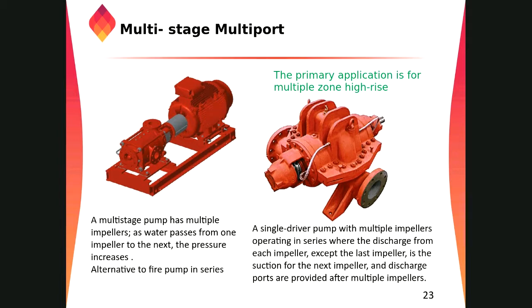When pumps are connected in series, let's say this is one pump and this is another pump, and these two pumps are in series connection, it is required to increase the pressure, right? And the parallel connection is required to increase the flow. That we'll discuss in a while. What I am trying to say is that in a high-rise building, they might need the series connection. One fire protection system will go only up to the 12th floor. After that, we need another tank and another pumping room to push the water to the levels after the 12th floor. In some cases, we can use the multi-stage multi-port pump.